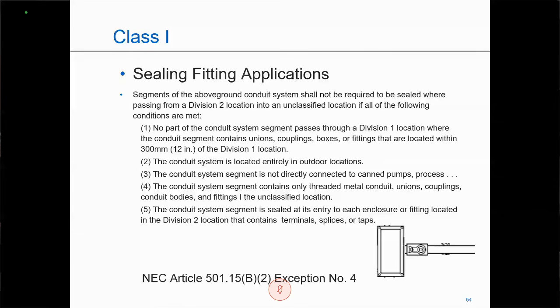If I move those units further apart, say 4 feet apart, for example, now I need a sealing fitting within 18 inches of each of those units. Also, one sealing fitting does not protect a line of equipment. So if I have a switch, I'm going to seal entering and exiting that switch. If that conduit then leads to a motor starter, I'm going to seal entering and exiting that motor starter.